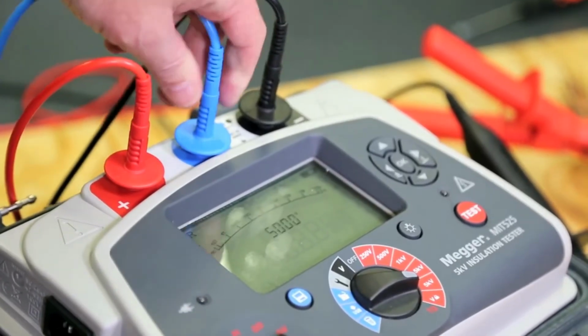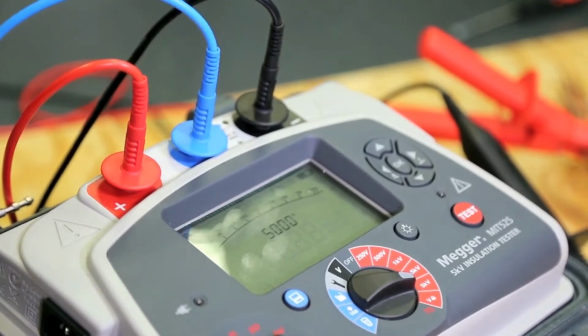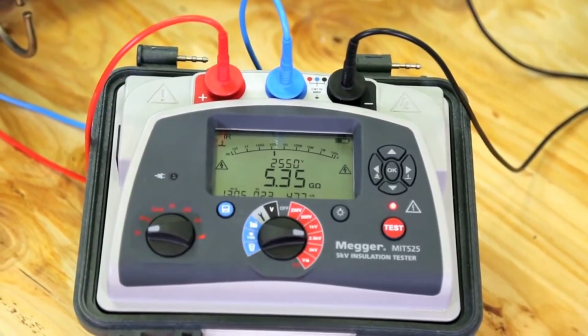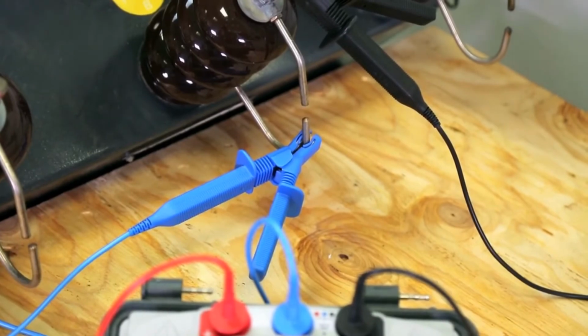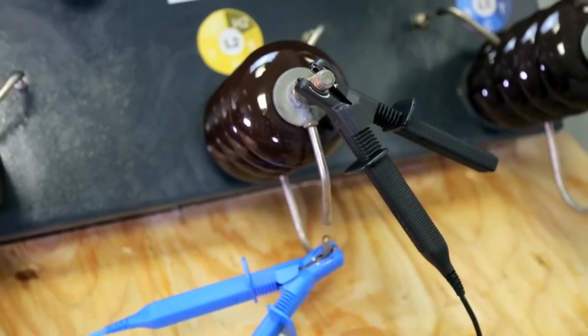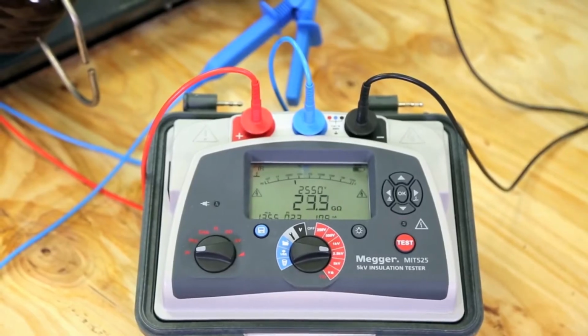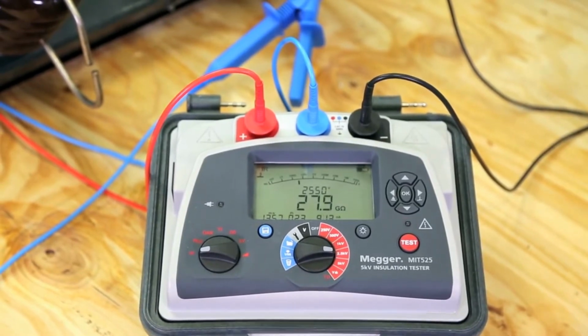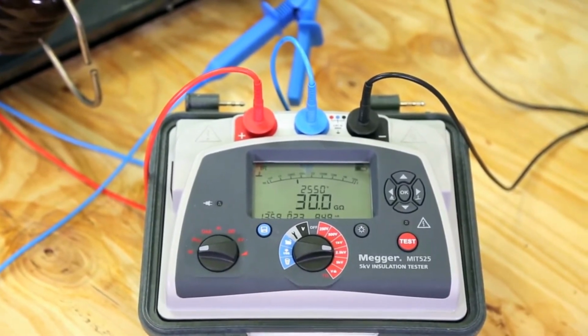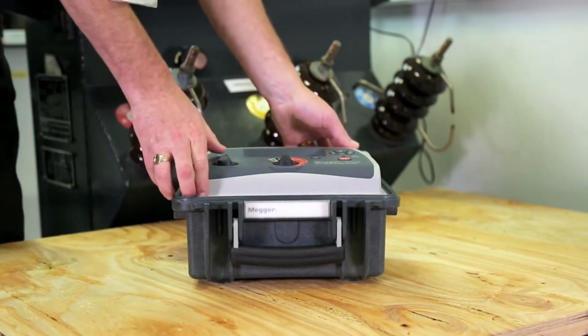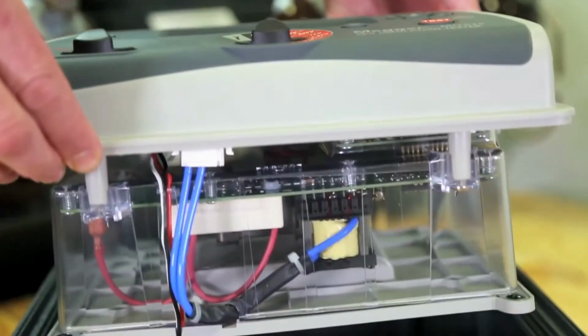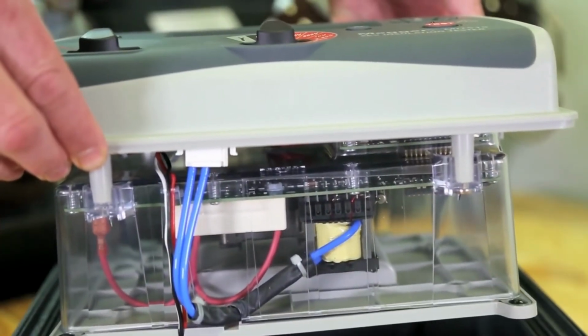The guard terminal ensures you measure the insulation that you want to measure. It measures and discounts any surface leakage current. It is key to the accuracy of the insulation test. That's why Megger's guard terminal performance is specified and offers unmatched accuracy. With a unique dual case design, the tough outer case protects a fire retardant inner case for extra reassurance.